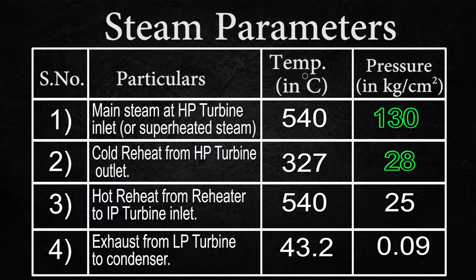We can see that the HP turbine handles 130 units of pressure and the IP turbine handles 28 units of pressure. Due to this, the HP turbine size is the smallest, as high pressure steam requires lesser volume than expanded steam. The LP turbines are the biggest in size because they have the lowest steam pressures, which require a bigger area to handle the steam flow rate.